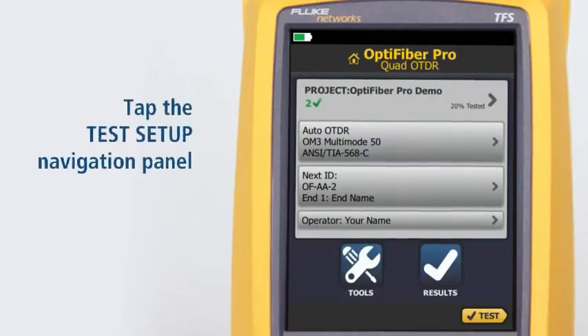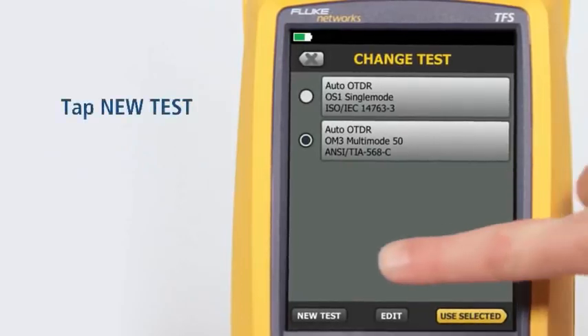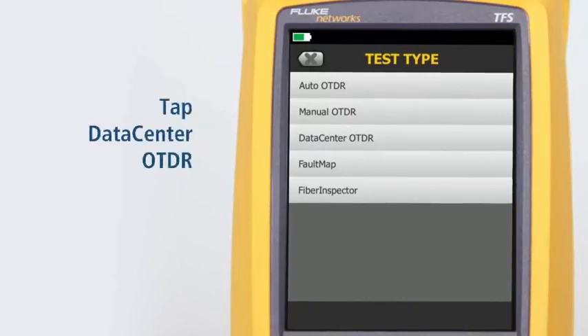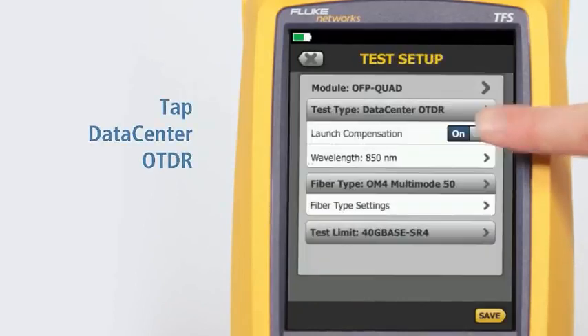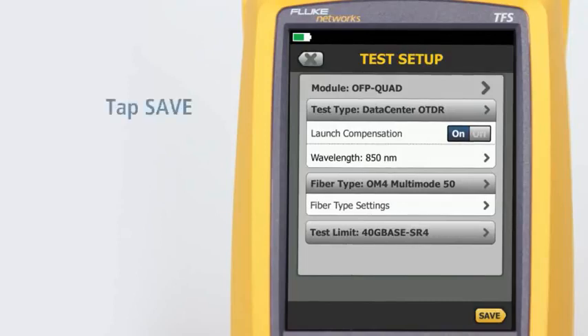Tap the Test Setup navigation panel, then tap New Test, then tap Data Center OTDR. Note that the Data Center OTDR defaults to only 850 nanometers for multi-mode fiber and 1310 nanometers for single-mode fiber. These are the wavelengths typically used in data centers. Tap Save.